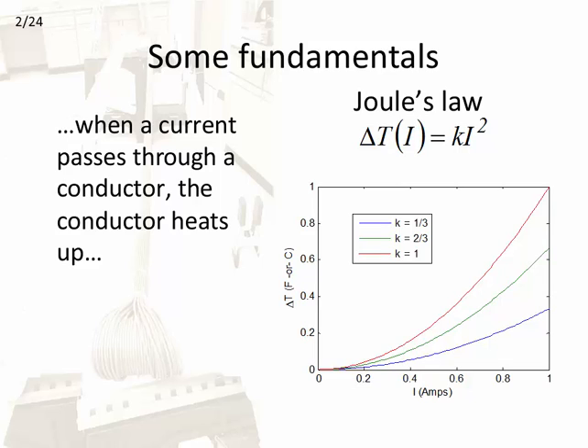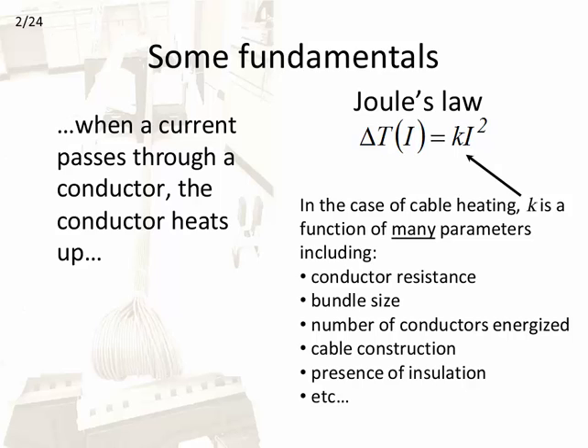So, some fundamentals of cable heating. Joule's law tells us that when a current passes through a conductor, the conductor heats up. In one of its simplest forms, Joule's law describes the temperature rise in terms of a constant K and the square of the current through the conductor. It is this constant K that we are most concerned with. In the case of cable heating, K is a function of many parameters, including conductor size, bundle size, number of conductors energized, and presence of insulation, among other things.